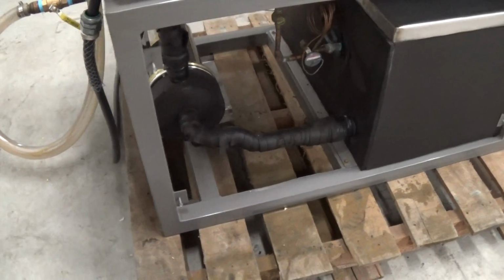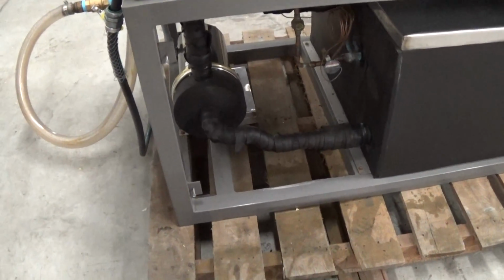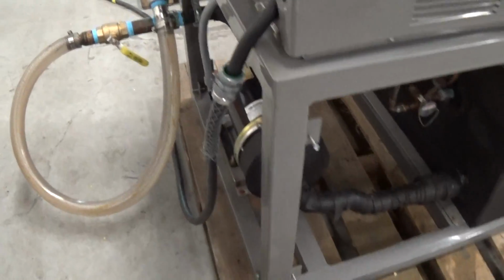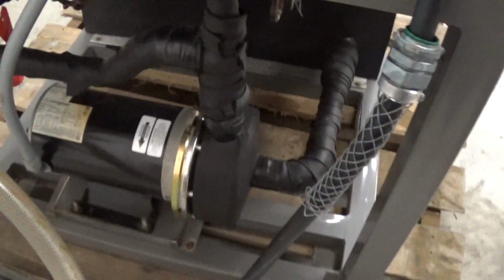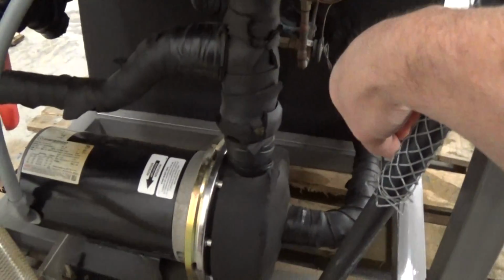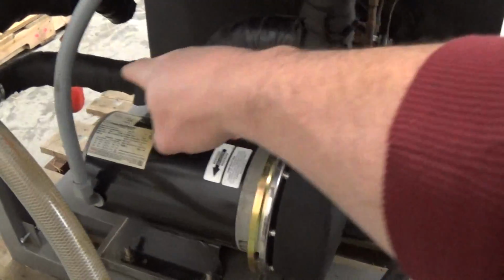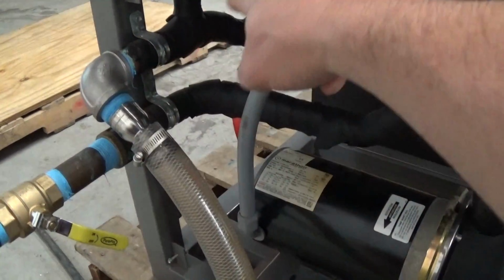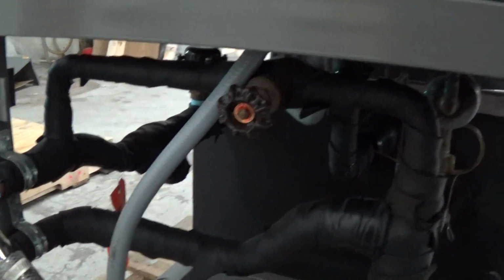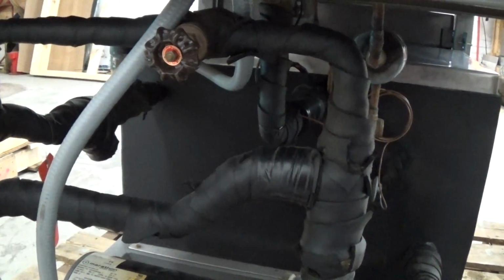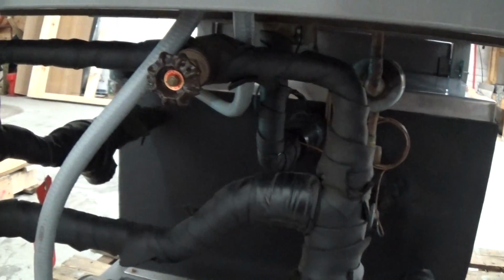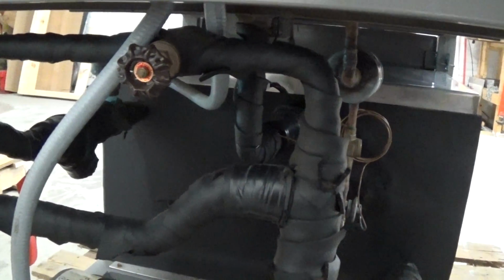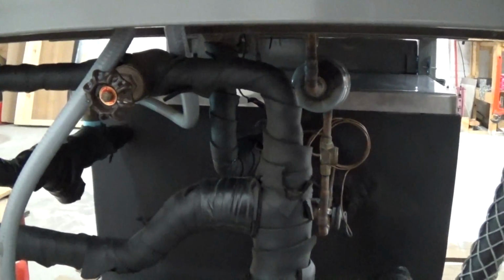Now for this application, we're actually going to be going through a heat exchanger. If we were going to be going to some jacketed tanks, we may have changed the way it's piped a little bit. But right now, it's piped pretty standard for a closed loop chiller. We're going to draw off the tank, out to your process, back into the chiller, and the chiller's heat exchanger. We do have an internal bypass here, meaning inside the chiller enclosure. We'll probably ship that cracked open like a quarter or halfway. That's to ensure there's always enough flow coming over the heat exchanger within the chiller.